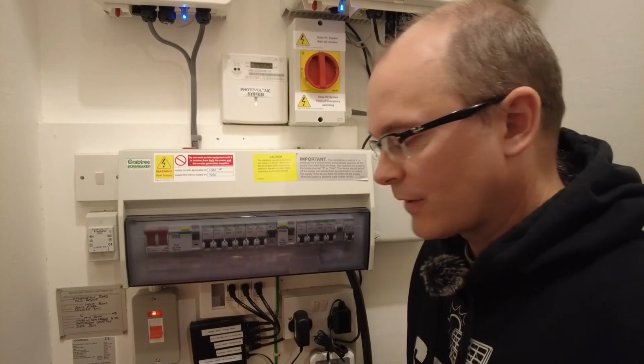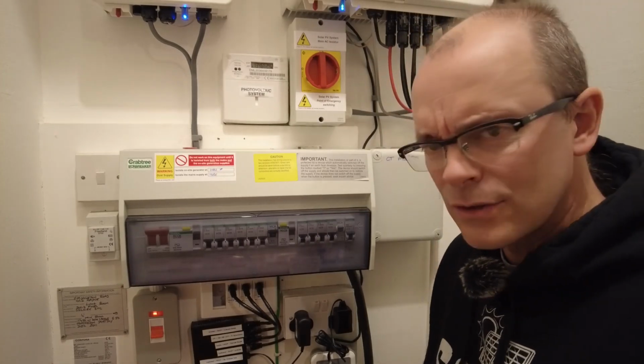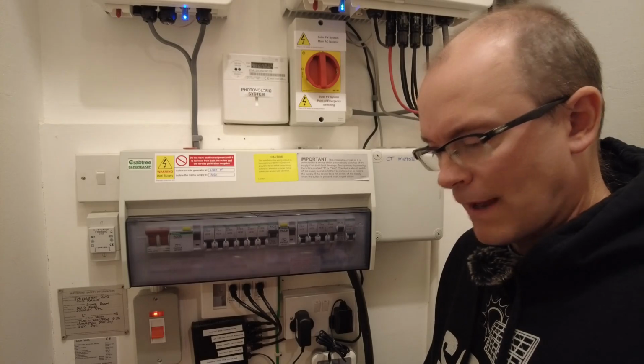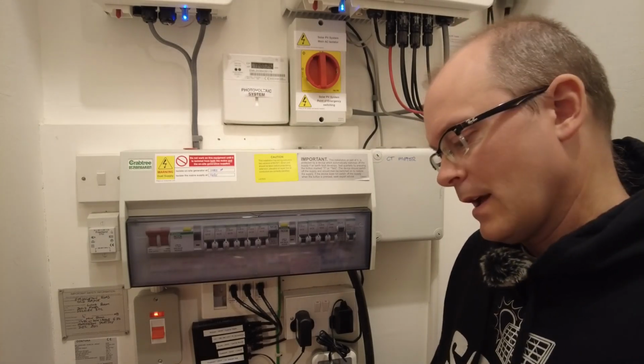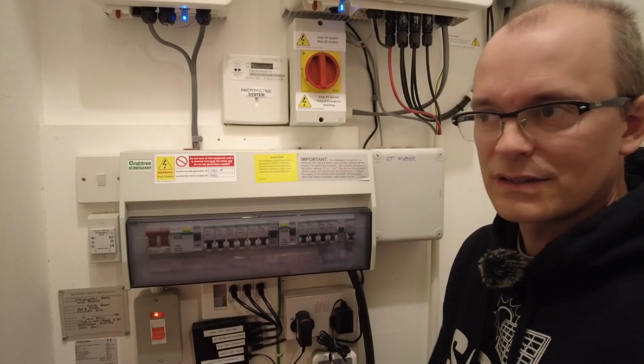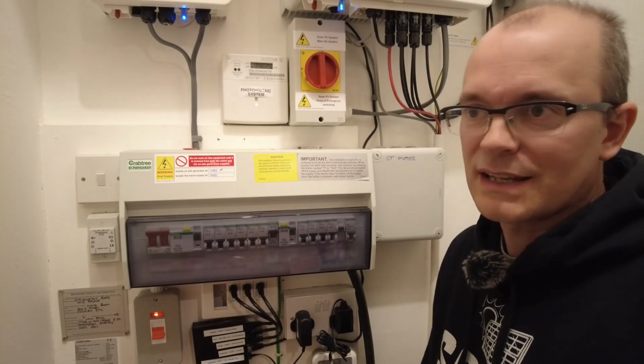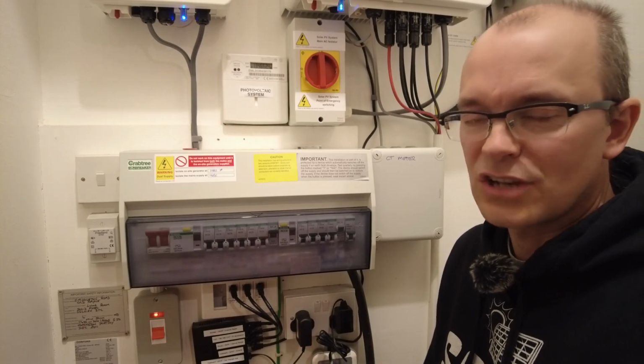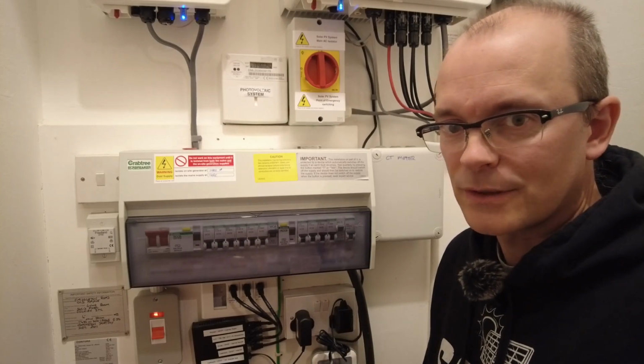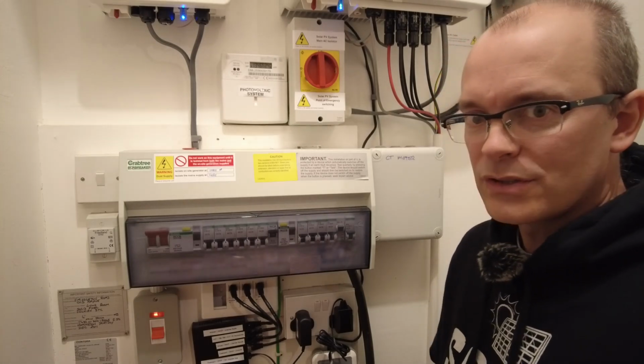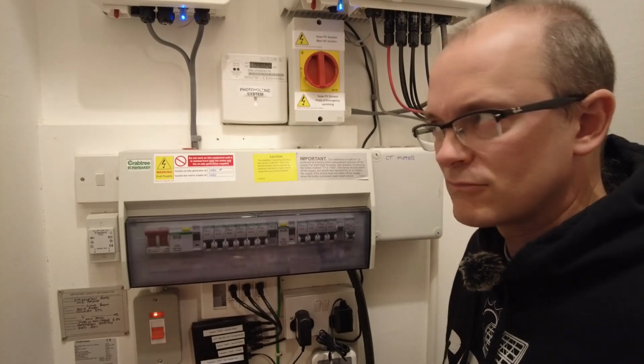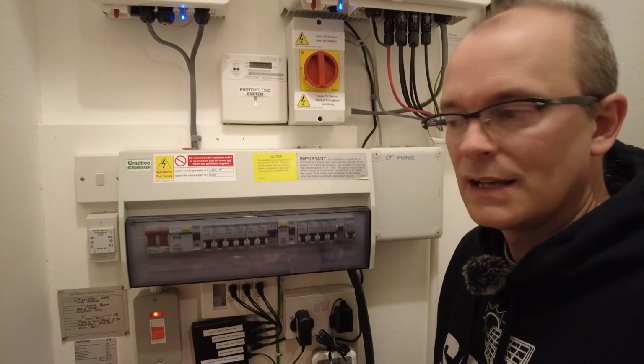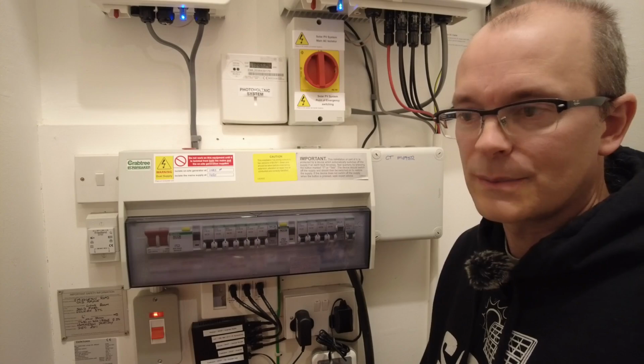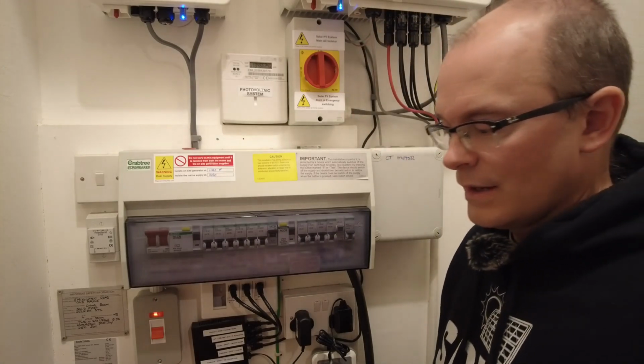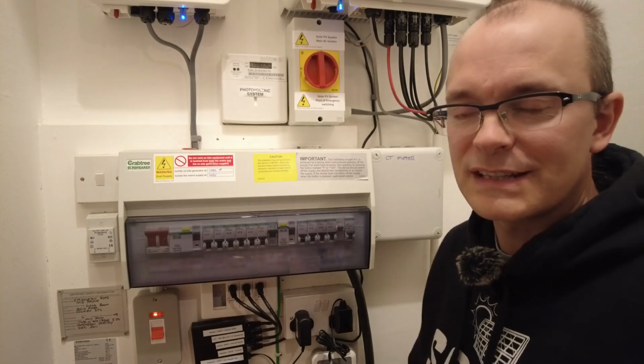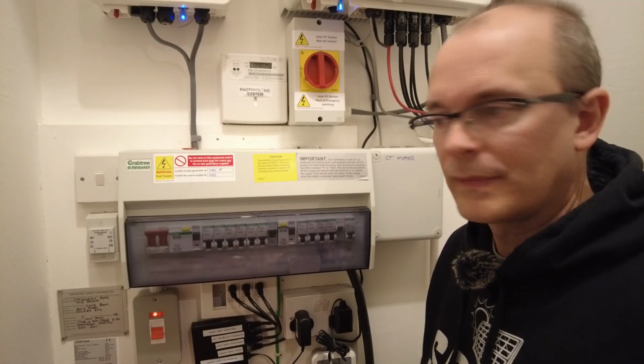So do I think the functionality can be improved? I do. For one thing, when it comes to maximum charging and maximum discharging, I want to charge up to a certain state of charge, and once you've reached that state of charge, I want the mode to then change to maximum self-consumption. Likewise with discharging, I want to discharge down to a level of about 20 to 30% and then revert to maximum self-consumption. That means the guessing game of how long you have to discharge can be taken out of the equation.